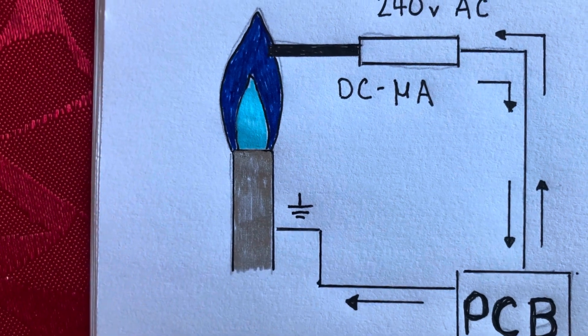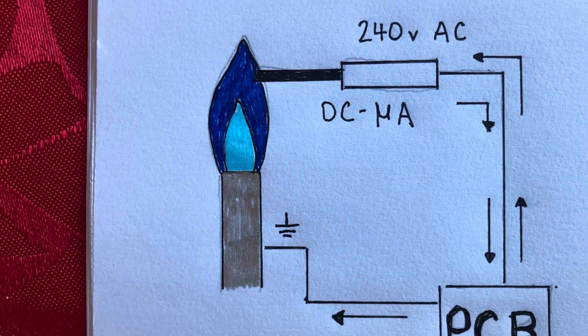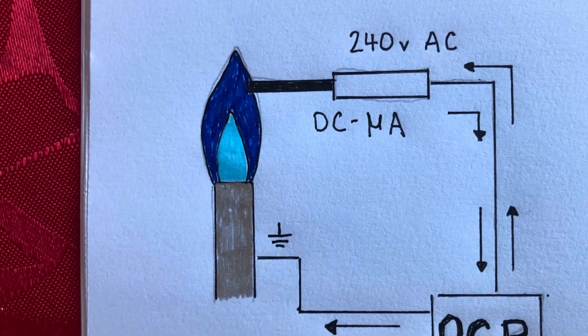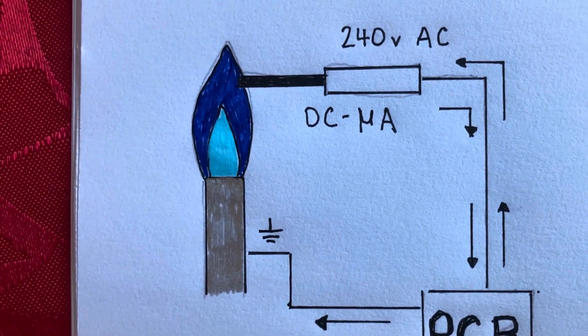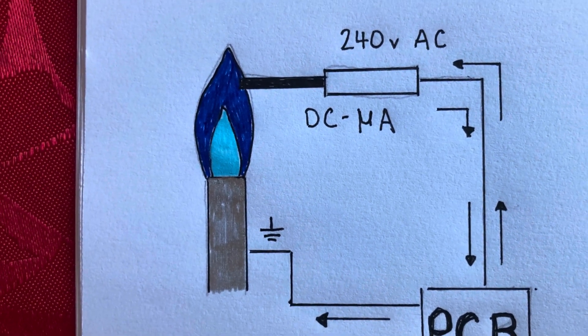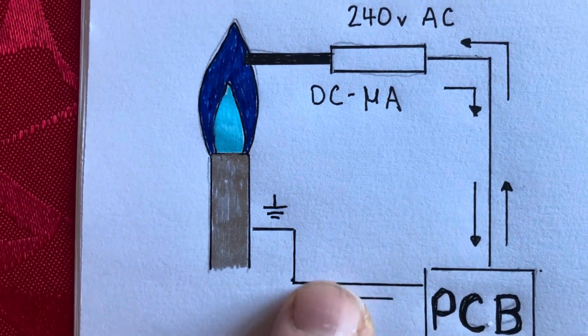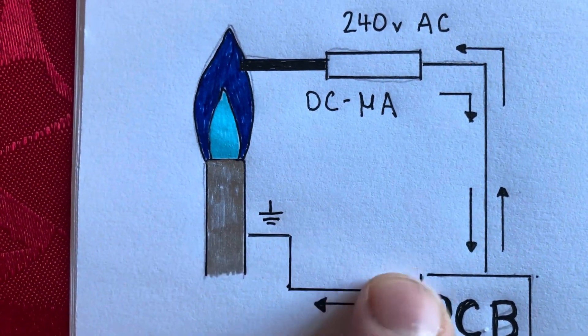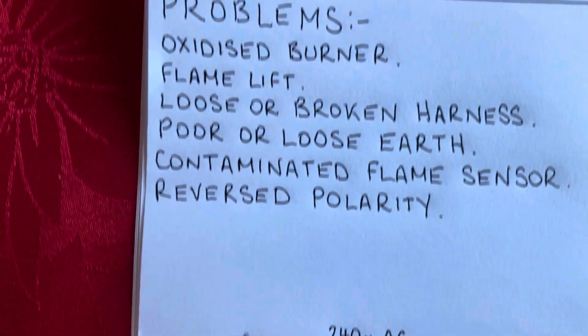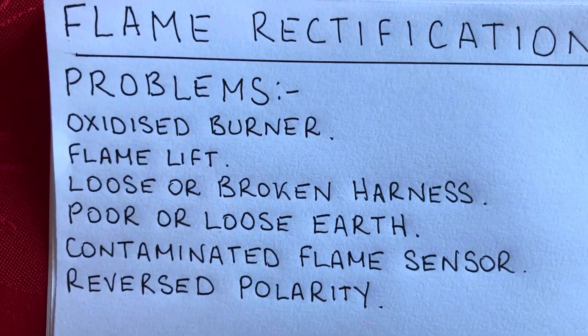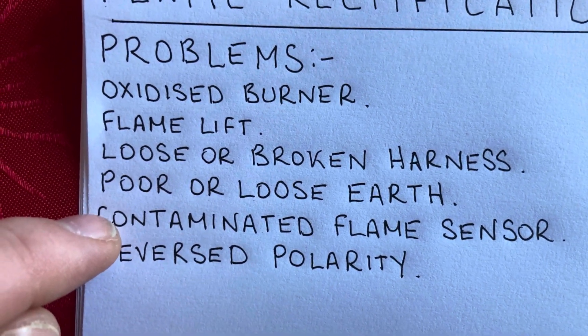Poor or loose earth is very important — we need a good earth. You can check this during your electrical checks before you start working on the boiler: polarity, short circuit, earth continuity, resistance to earth. When you do that you can test the earth from the main earth point on the boiler, and if you haven't got a good earth it can cause poor rectification.